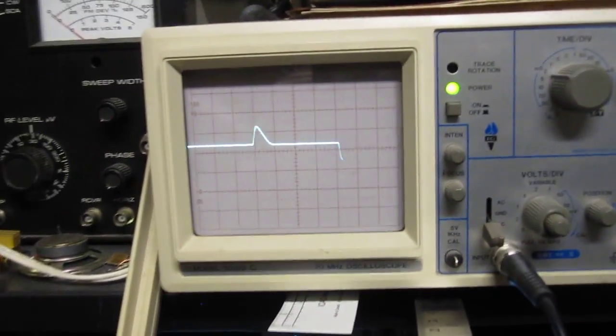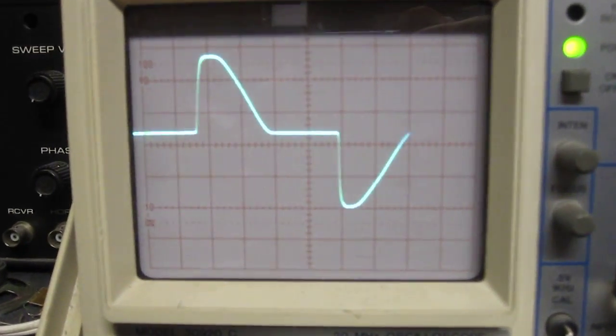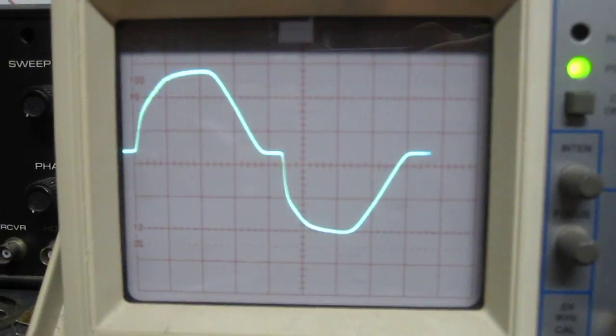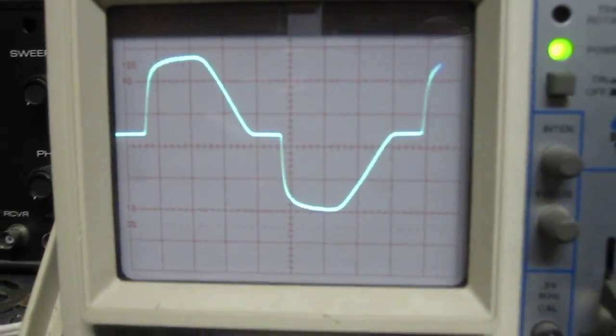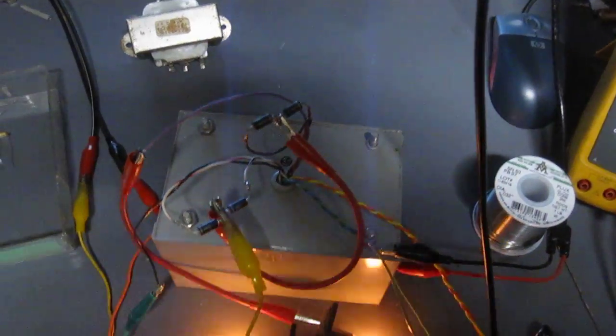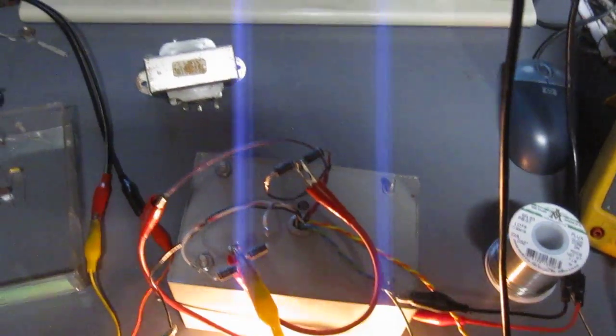If you look, it looks like a typical SCR or Triac chopper waveform, but what we've got going is actually a saturable core reactor with rectifiers included to give this waveform.